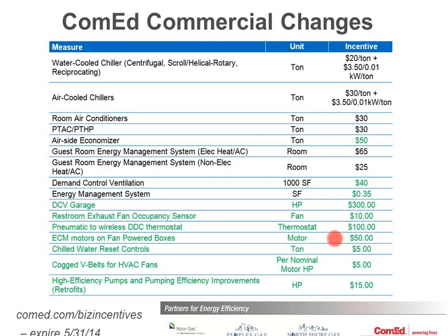Most ECM motors on a fan powered box just go in there and replace the old PSC, and they do not change the speed dynamically based on what the DDC controller wants. In order to get the rebate, you have to do that, so you have to come up with your own little sequence to make that happen. There is a new rebate for $5 per ton for adding chill water reset controls to your chiller plant. There's rebates for cogged V-belts, $5 per horsepower, and then there's some new pumping rebates you could check out.